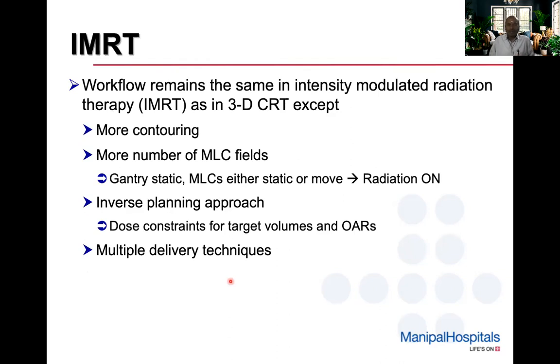When we talk about intensity modulated radiation therapy, IMRT, the workflow remains more or less the same as in 3D CRT. The key differences are that we have to do a lot more contouring of normal structures and use more MLC fields. In these fields, the gantry remains static but the MLCs will either remain static or move at the time of radiation delivery.